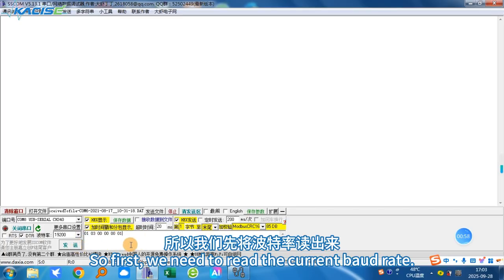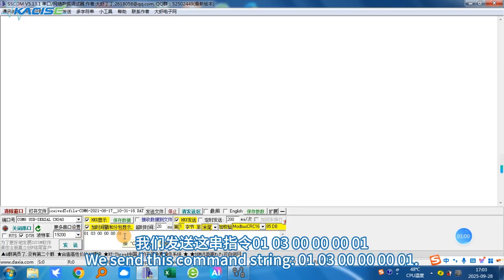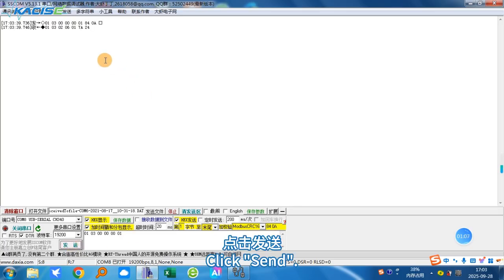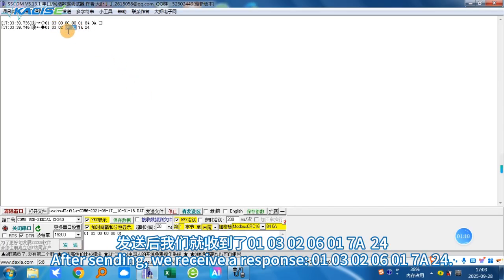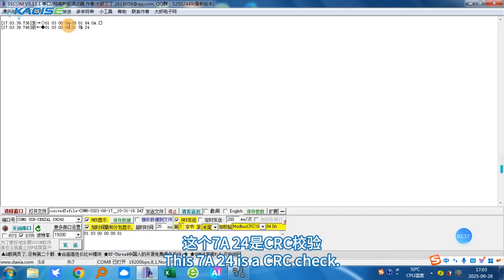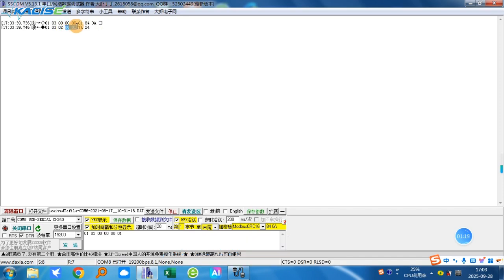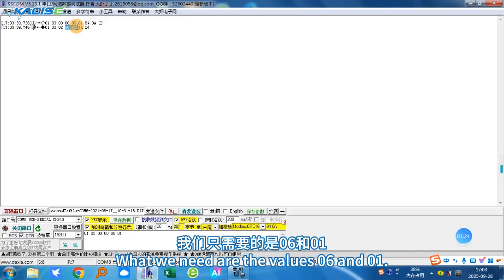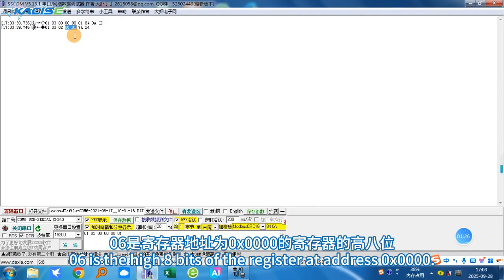So first, we need to read the current baud rate. We send this command string 010300000001. Click Send. After sending, we receive a response 0103020601 7A24. This 7A24 is a CRC check, so we don't need to pay attention to it. What we need are the values 06 and 01. 06 is the high 8 bits of the register at address 0x0000.